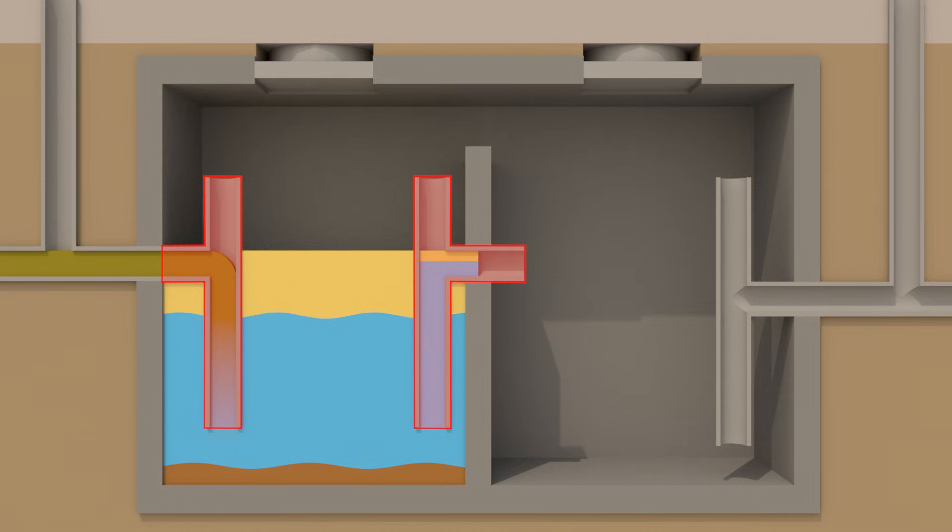The inlet T and transfer T slow down the flow, allowing the water to cool, which increases separation and solidifies the FOG, making later removal easier.